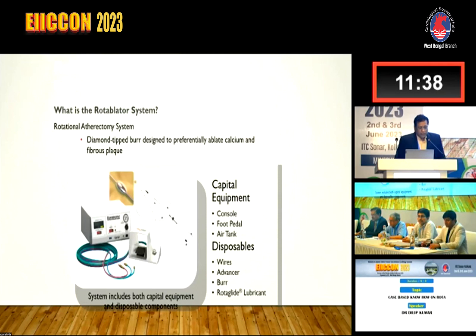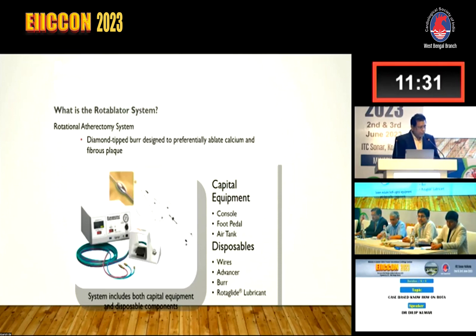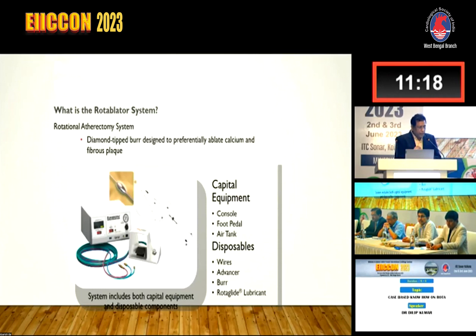Let's get familiar with the rota ablation system. We now have rota pro as well as the original rota link which we've been using for the last seven to eight years. Both have a console, an advancer, and a foot pedal. In rota pro, there is no foot pedal - on the advancer there is a knob which you activate to start rota ablation, and push again to stop. Everything is under your control in rota pro.